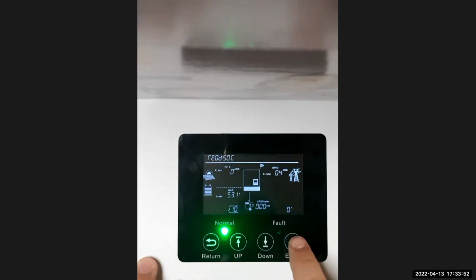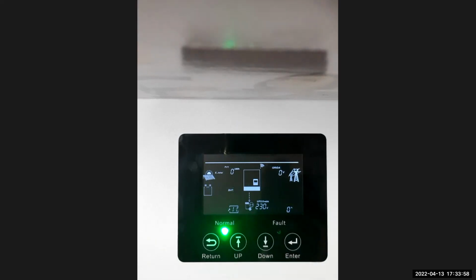So that's what number 10 is, just to tell the inverter whether it must work with volts or percentage on the parameters that you're giving it. Number 11 is my cut-off voltage. Now, number 11 and number 12 work hand in hand. Number 11, you can't take it higher than number 12 is. So you'll see I won't be able to take it higher than 15%. That's the same as it will be when you get it out of the box. So your cut-off voltage can't be higher than your number 12 setting.